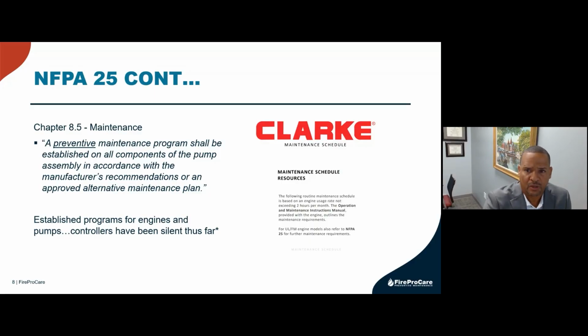So, Chapter 8.5, NFPA 25. Remember that it requires a preventive maintenance program be in place, and you should be using the manufacturer's recommendations. If nothing else, remember that. Chapter 8.5, NFPA 25. The PM program is required.